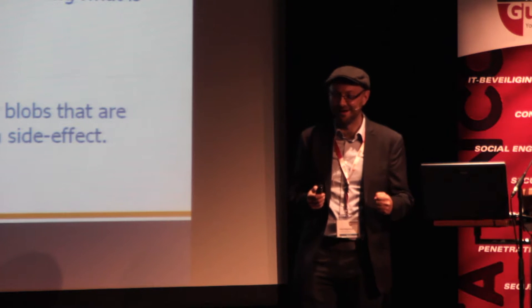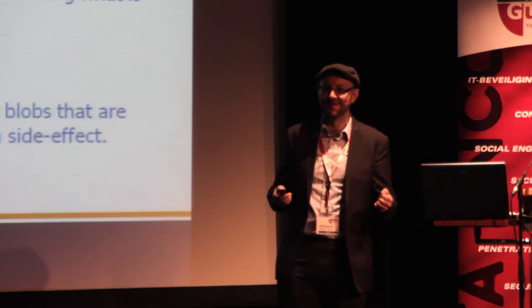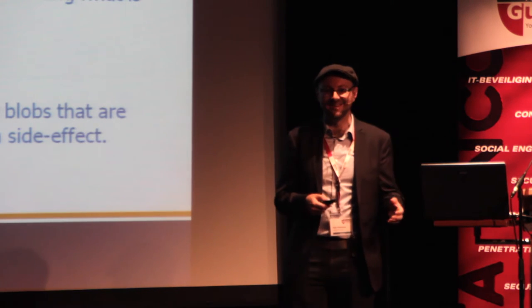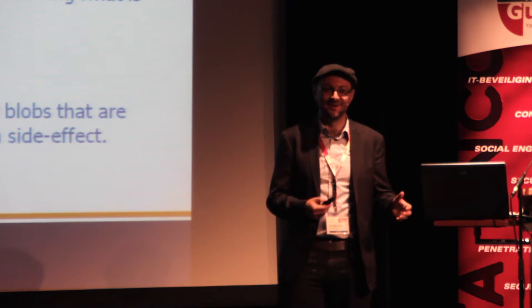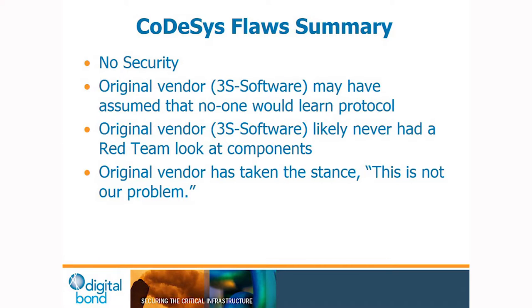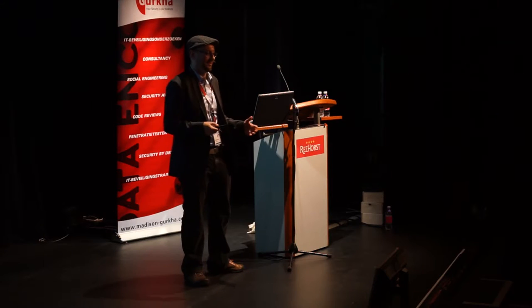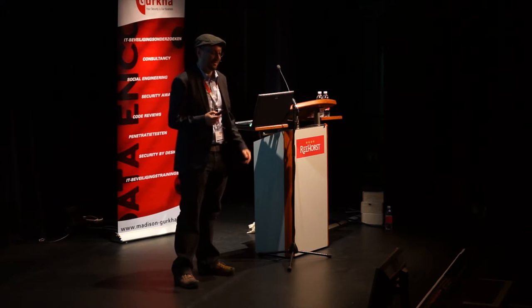What really gets me is that because of how CODESYS works, when you write a ladder logic file, it's really just a binary blob of executable code. When you upload that to the PLC, it's going to run with root or system privileges. The process takes that binary blob, copies it into memory, and jumps into it — executing whatever you uploaded. So there's really no security. The original vendor, 3S Software, probably assumed nobody would figure out how the protocol worked. They've actually published something to the effect that they don't expect their protocol will ever be secure from attackers. It's pretty likely they never had a red team look at this software, because a red team would have immediately said this is bad.